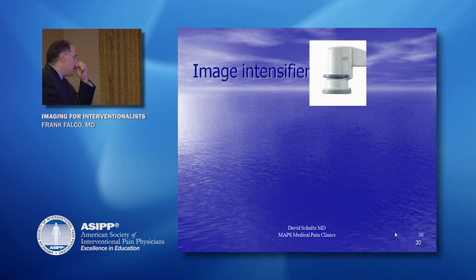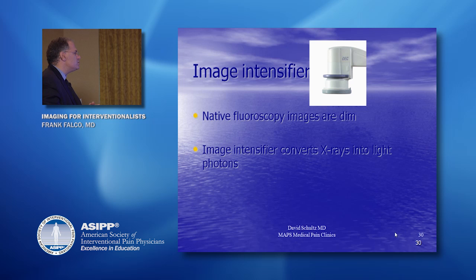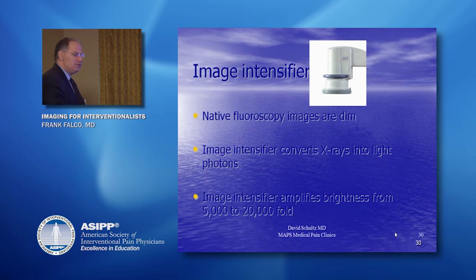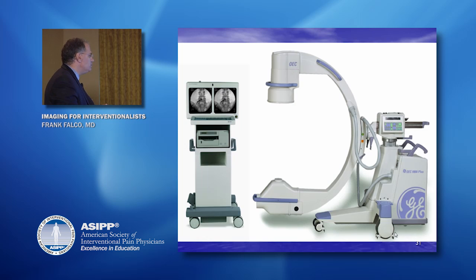So there's our II, the image intensifier. Native fluoroscopy images are dim. The image is intensified. The image intensifier intensifies the image. It converts X-rays into light, hitting the phosphor, and those photons are converted into an electrical signal. And the image intensifier is able to amplify the brightness of the image 5 to 20,000 fold.